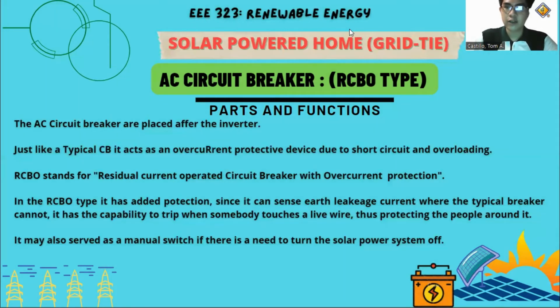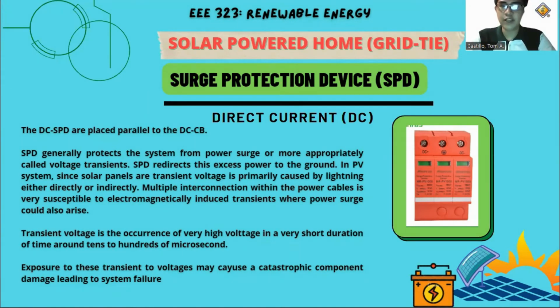So what is earth leakage current? It is the unwanted, unused waste current flowing from a live conductor or terminal to the ground or earth through the ground conductor or any other conductive path. Earth leakage with a high current mostly occurs in electrical transmission lines and can be called an earth fault. It also occurs in transformers and other electrical devices. Earth leakage current flows through the ground conductors to the earth. If there is no grounding or earth system available, or there is improper grounding, then the earth leakage current will try to flow through any other conductive path. An example here is the human body. Although it is not possible to make an electrical insulation with 100% no leakage, it should not cross the limit. Next, the surge protection device for direct current.